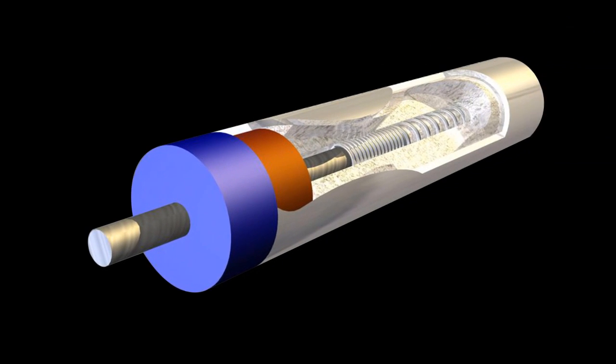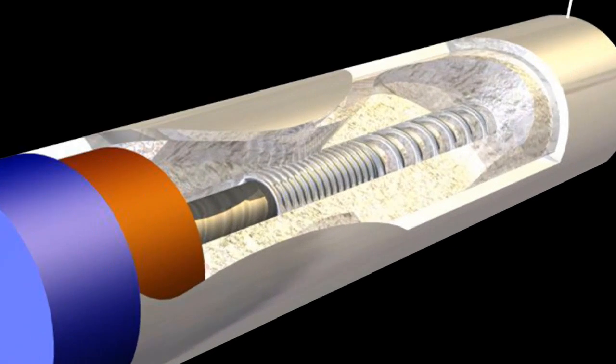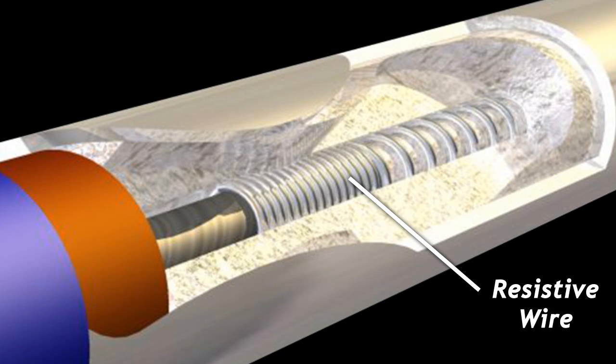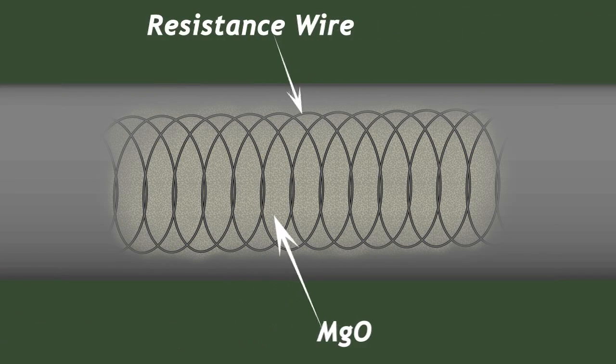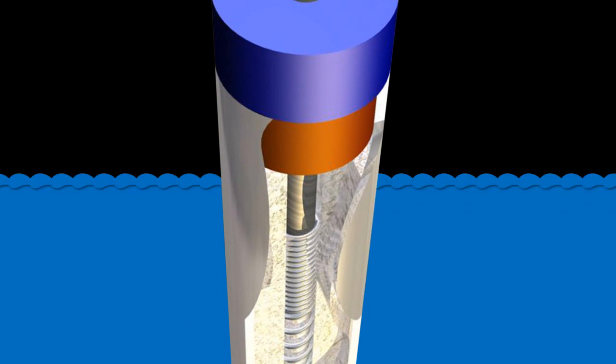A basic tubular element has a metal sheath with a nickel chromium coiled resistive wire running through the middle. The tube is filled with magnesium oxide and rolled so that the wire is now tightly packed inside the tube and then sealed to protect it from moisture.